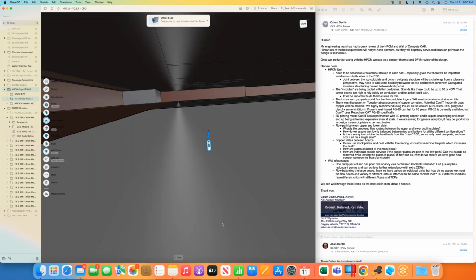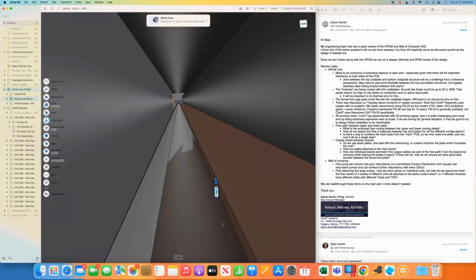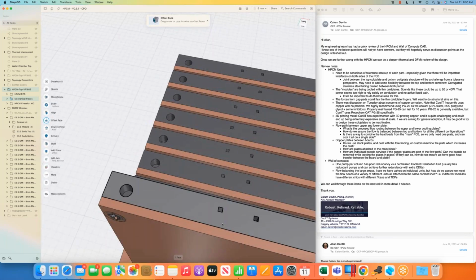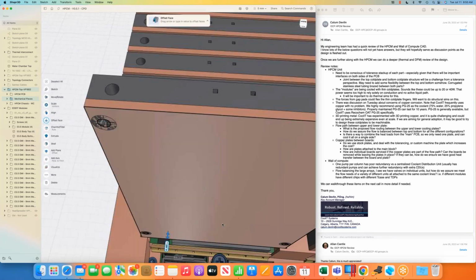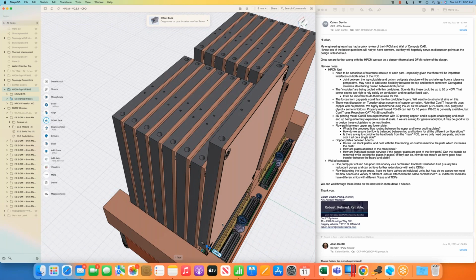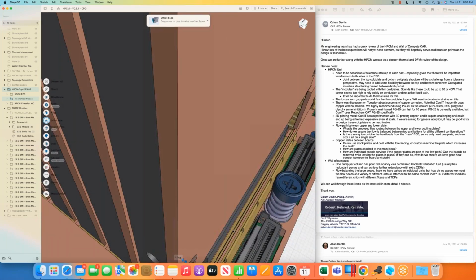Yeah, so I think ideally you try to eliminate fingers coming from either side, and make it so it's only coming from one side. So that skinny part coming down from the cold plate of the module goes down as far as it needs to, without needing the copper that's in between the gold connector right now. It would be good to eliminate that and just have it come from the cold plate on the module itself. Oh, so we turn this into a double-sided spring-loaded single piece. Oh, that's interesting.